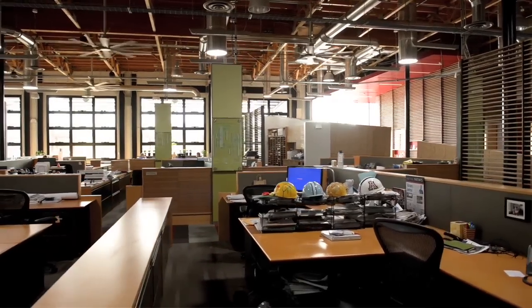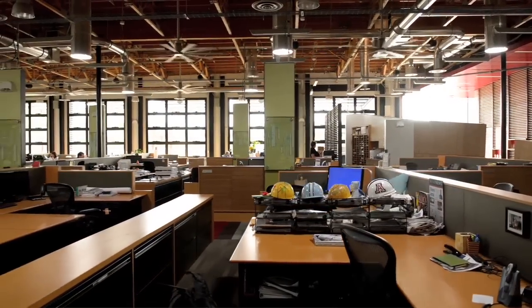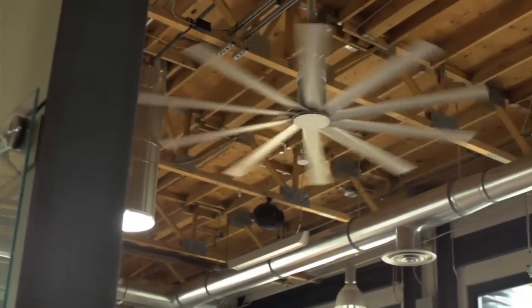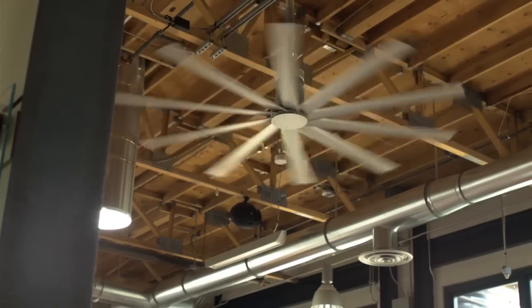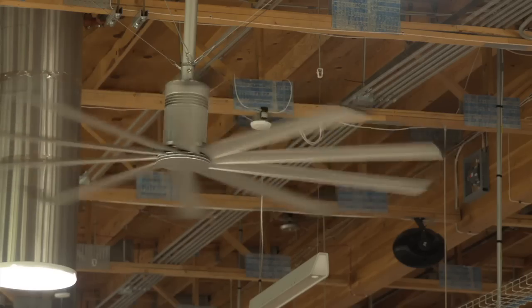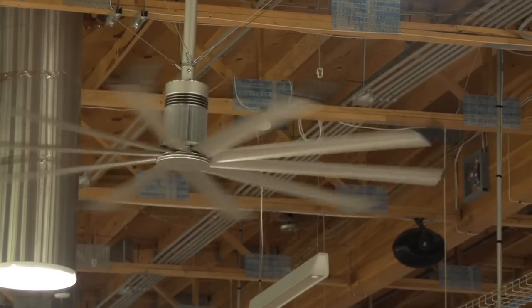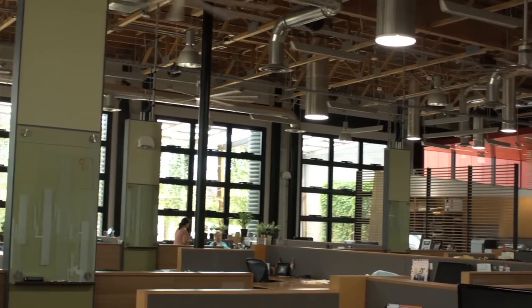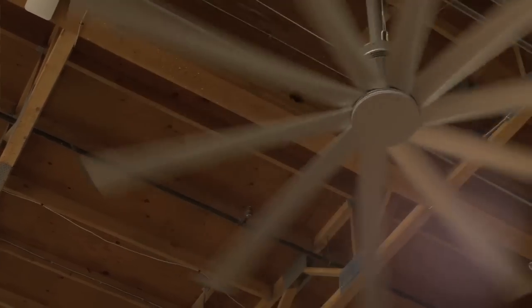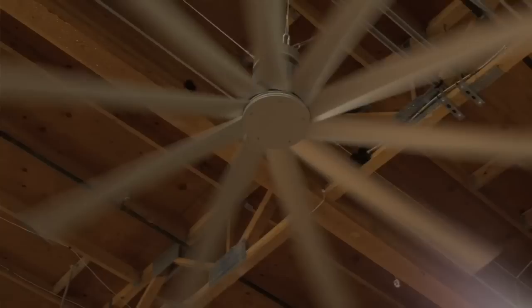Thermal comfort in the summer is taken care of by elevated airspeed. In the winter, there's a concern about draft, especially with overhead circulator fans running. It's important that air movement in the space not exceed 30 to 40 feet per minute, which is where draft can occur. Whatever your air distribution strategy, you need to maintain good mixing without creating draft, keeping air speeds below that threshold at occupant level. For projects using large overhead fans, that typically means slowing them down enough to still mix the air sufficiently without creating a draft.